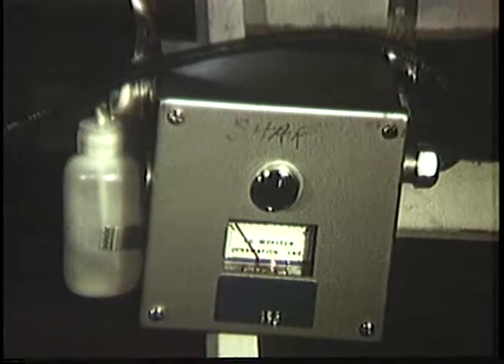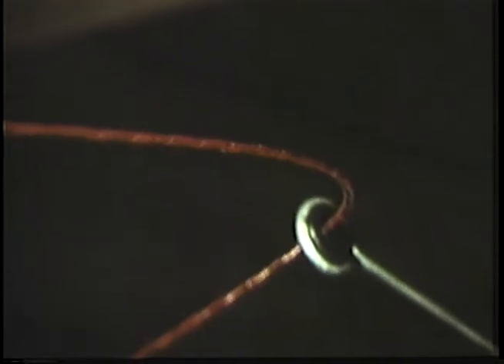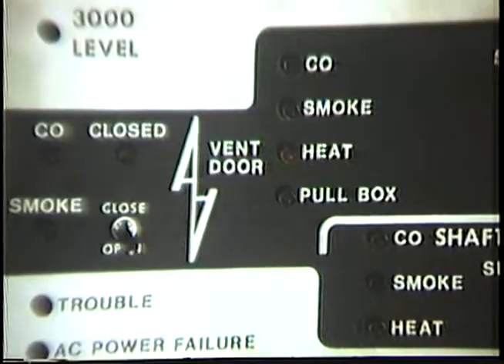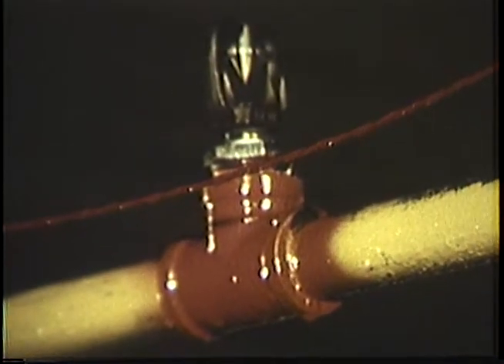Because a primary killer in a fire is carbon monoxide, a second detector type warns of the presence of CO gas. The two types of sensors complement each other, since both smoke and CO usually accompany any fire likely to be encountered in an underground mine. A third sensor, selected for high reliability, consists of thermal wire which melts at a temperature of about 155 degrees Fahrenheit. Although ionization and CO detectors may occasionally alarm because of diesel equipment or blasting, the melting of thermal wire sensors represents an almost foolproof indication that fire exists in a protected area.